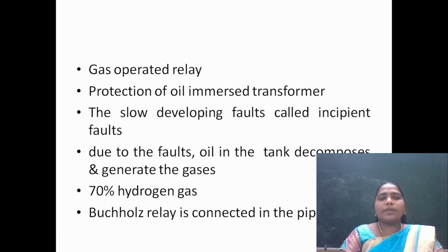The fault that majorly occurs in the oil immersed transformer is the incipient fault. Incipient fault means a slowly developing fault. Due to this fault, the oil in the tank decomposes and gases get generated. 70% of the gas is hydrogen gas. We all know that hydrogen is a lightweight gas and it easily moves upwards. And the Buchholz relay is connected in the pipe.